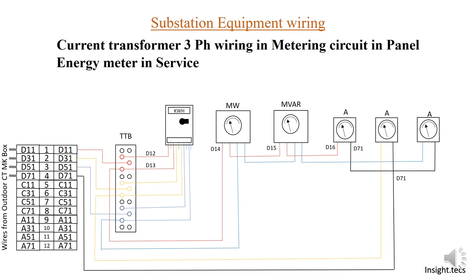When the energy meter will remain in service, what will be the current path? The use of the TTB is such that you can keep the energy meter in service and bypass it. If you have to work on the energy meter, you can do so without disturbing the rest of the circuit. When the energy meter is in service, the current will be passed — the light dot represents the current. This is a continuous process, shown as a small animation.